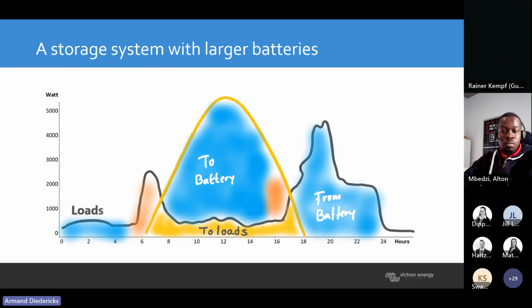So if you have an industrial or commercial site and the client is on Ruraflex, you need to avoid the NMD. The NMD is normally from 6 to 10. Then you can put a mechanical interlock, or you can program the unit, general flag, dedicated AC ignore, and say, don't allow Eskom on that stage. So provide power from the sun, the battery, and the generator. Once the stage from 6 to 10 is over, it can provide power again from the grid. That's to avoid the large bill. That's the main function of ESS.